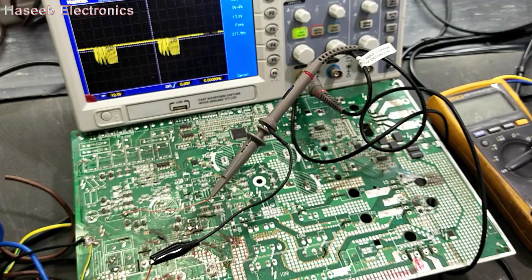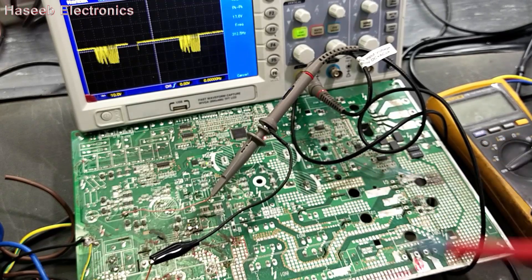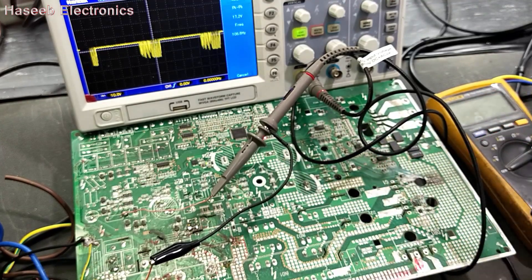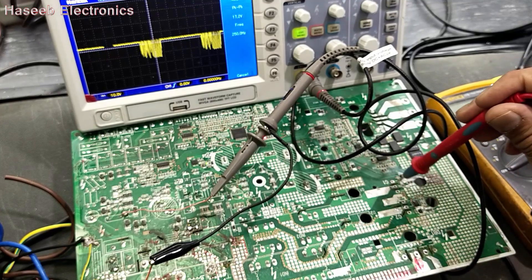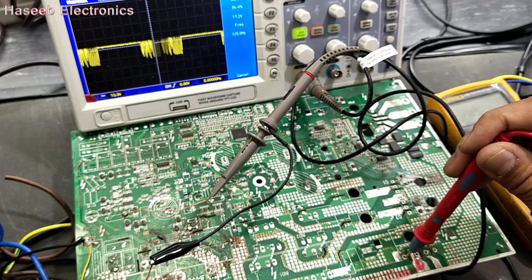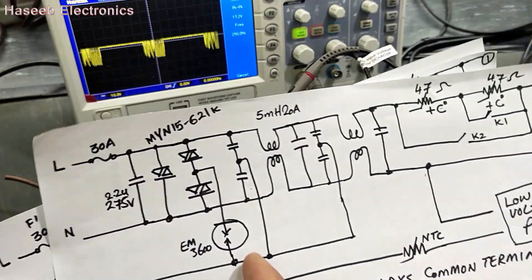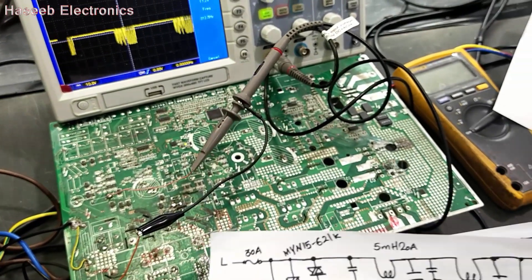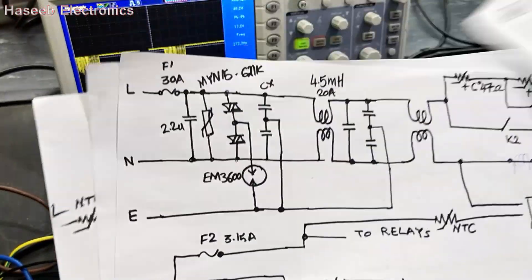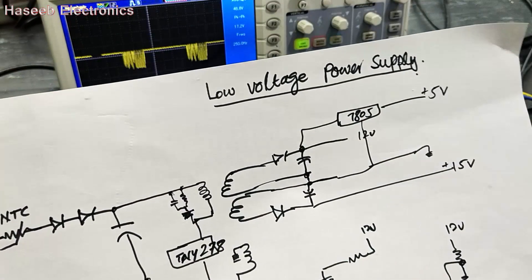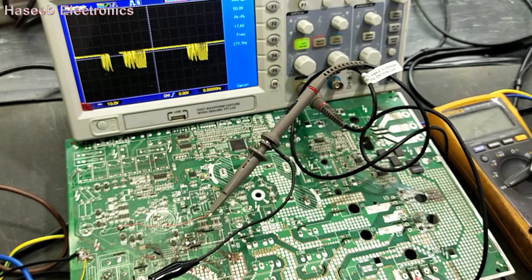First, I will show what communication is. This time I have just only the outdoor unit board. This board has a fault — abnormal voltage and PFC fail, meaning power factor correction fail — because this board does not have IGBTs and does not have a bridge rectifier. This is a series of videos: in the first series I discussed input filter and protection circuit, then PFC circuit, then low voltage power supply. Today we are going to discuss communication.